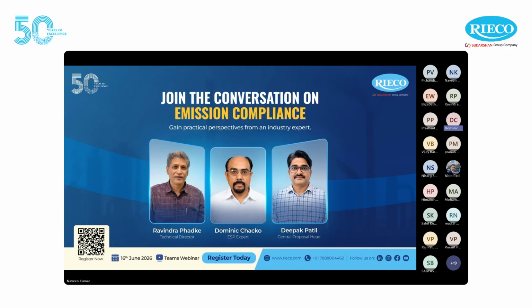An example is that I have seen two identical ESPs in a paper plant. Basically, those ESPs are coal-fired ESPs, but in a paper plant. Both are identical, and both are supposedly loaded identically. But one of the ESPs is working very fine, the other one is not. There is always an emission, and the customer has done a lot of work internally addressing the alignment and things like that. But one key point that they have missed is near the inlet expansion joints, in an area where it's not very easily visible. There was a huge wearing out of the expansion joint, and through that a lot of air leakage was taking place. This somehow escaped the attention of the customer, and these kinds of leakages have two impacts.